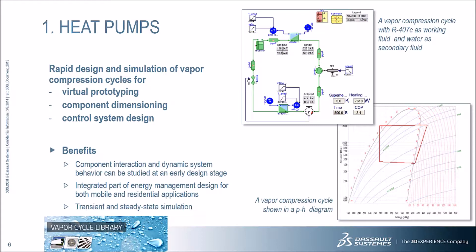Component models for compressors, expansion devices, and heat exchangers can be combined to investigate different architectures at varying levels of detail. Both transient and steady-state operation can be simulated. The system diagram shows a typical vapor compression cycle. The working fluid, here R407C, absorbs heat from a low-temperature heat source, typically ambient air or an available water reservoir. The vapor is first compressed and then condensed at a higher pressure and temperature level, thereby heating the target fluid. In this example, water is used in both the heat sink and source, though the target fluid is easily replaced by air or an incompressible fluid from the liquid cooling library.